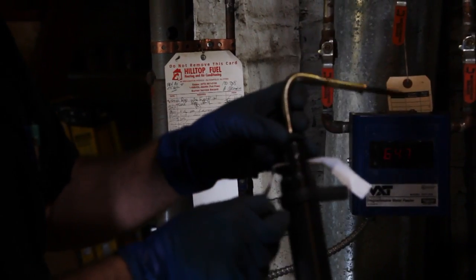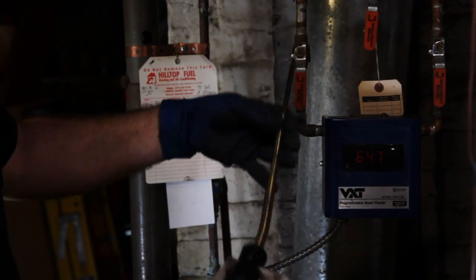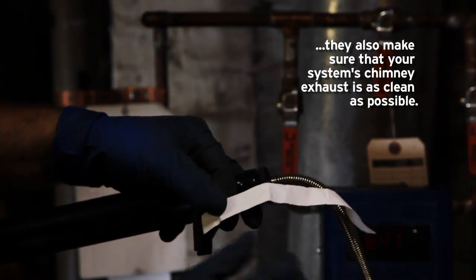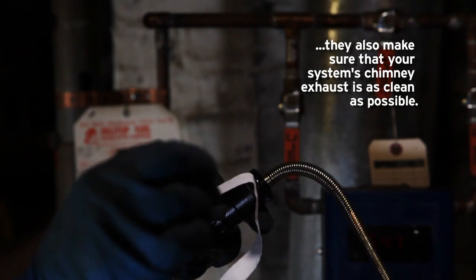This is a smoke tester. What you're doing is drawing through here, out of the smoke pipe, to draw the gases that are going up the chimney. Our reading is dead center at zero. If you had any situations where it was dark or black, then you have to adjust the air on the burner to give yourself a little bit more air.